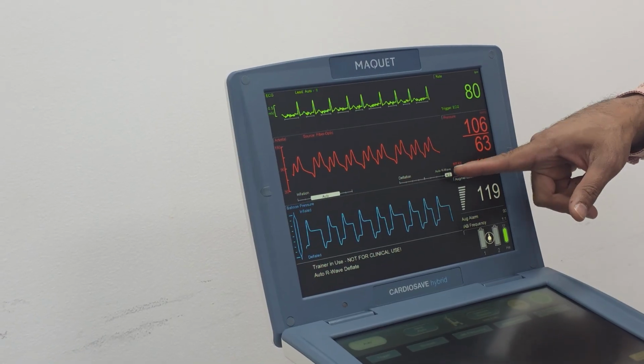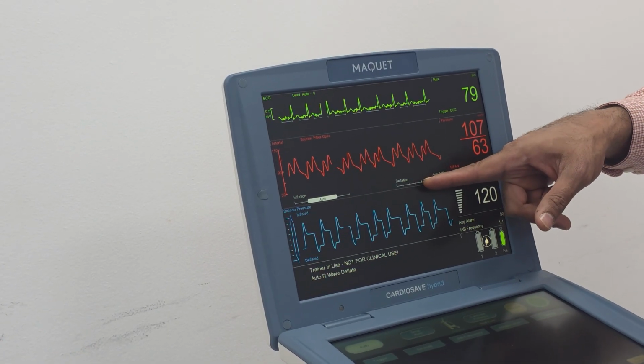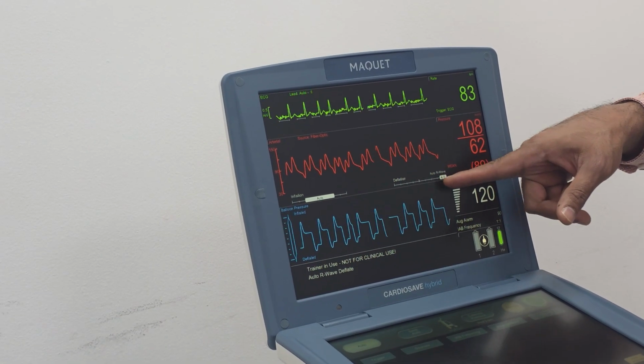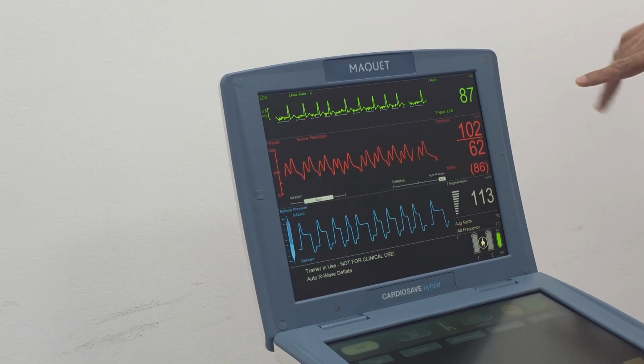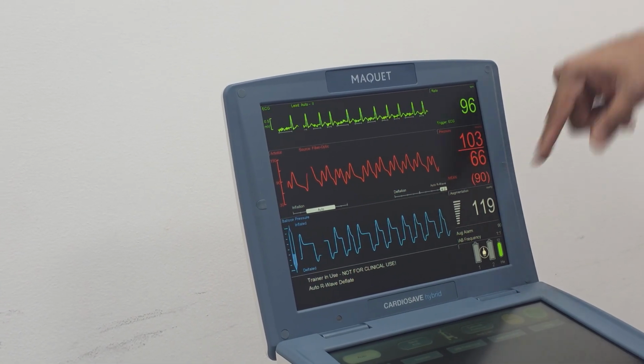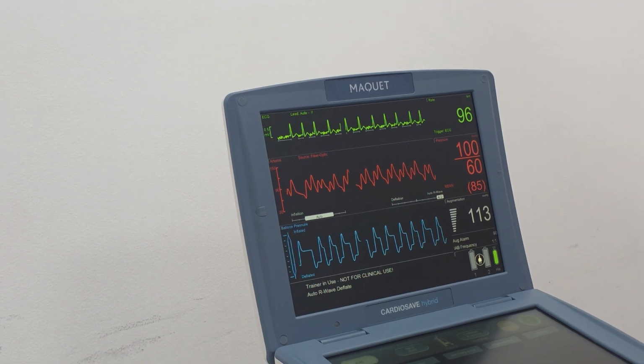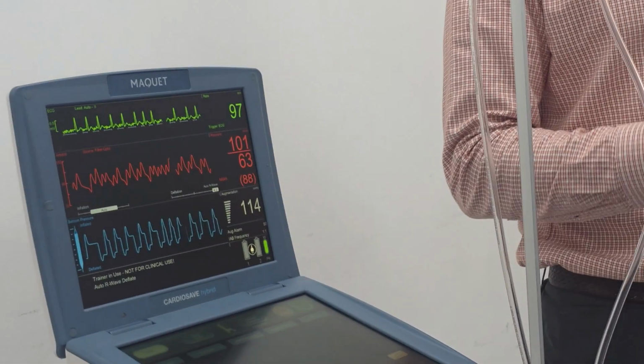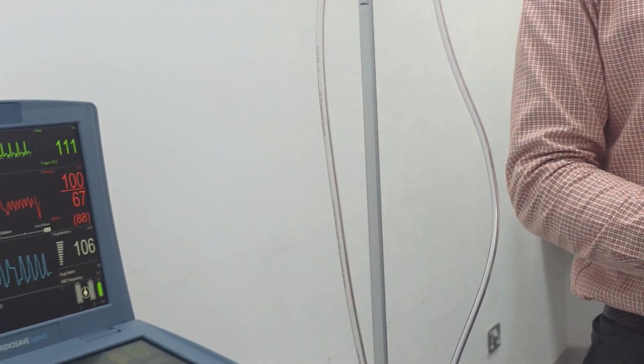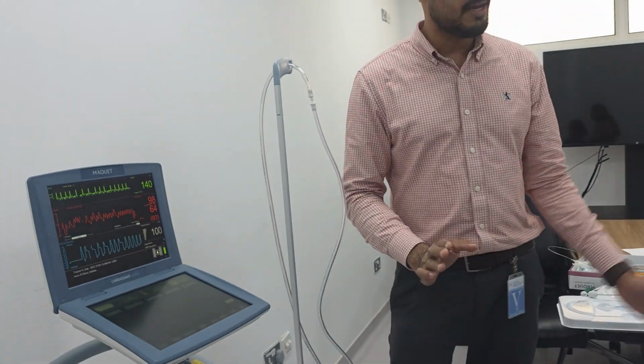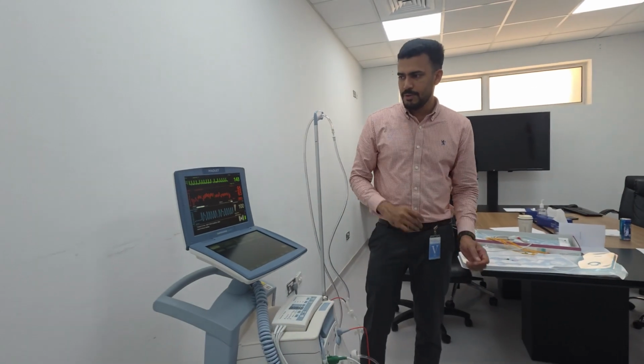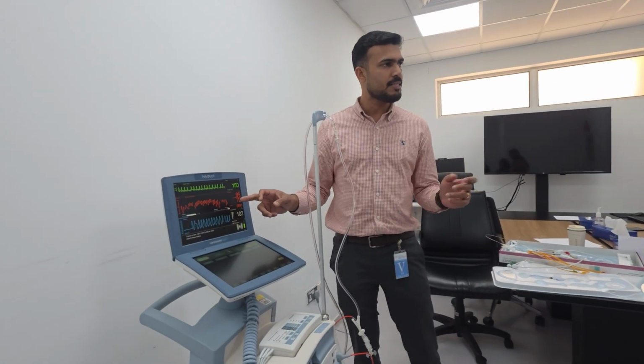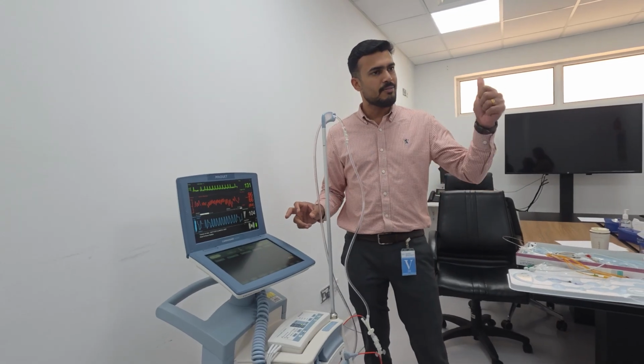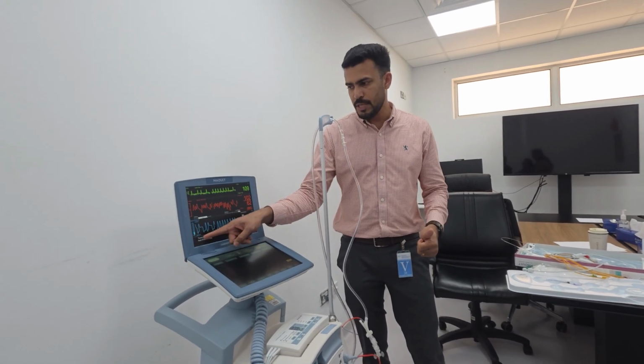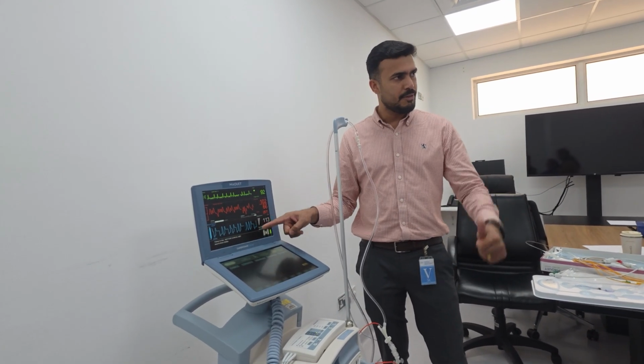It was supposed to be in the middle, the deflation automatic, but here it delayed. So it delayed to the extreme end. When there is an R wave, the balloon will deflate immediately. It's a feature called auto R wave deflate. It's a clinical feature. Not a new feature, even the CS300 has it. Whenever there is an irregular arrhythmia like AF, when there is an immediate R wave, the balloon should deflate. That's why you can see this auto R wave deflate.